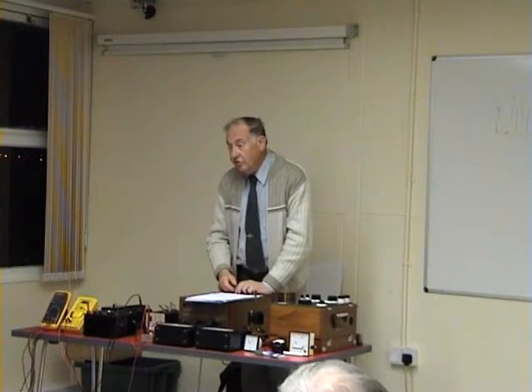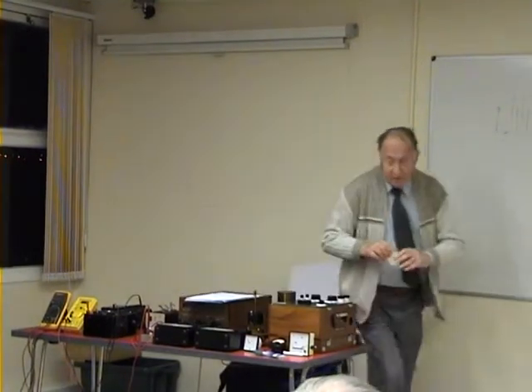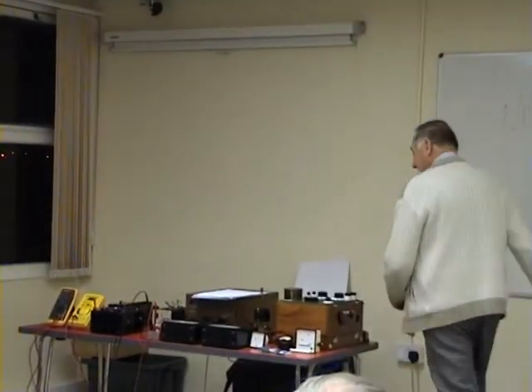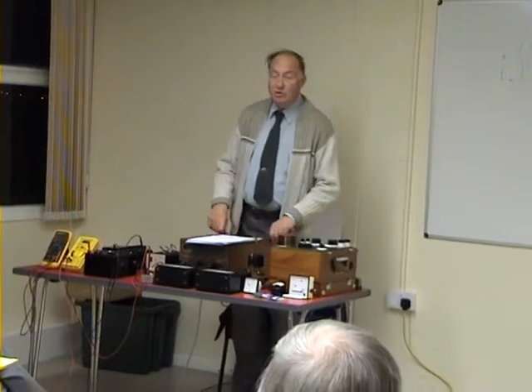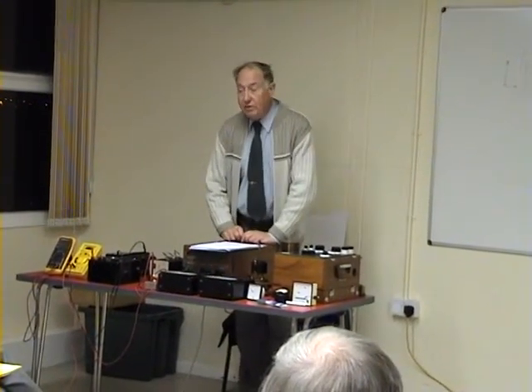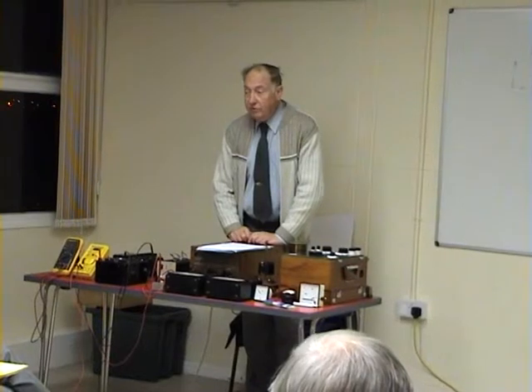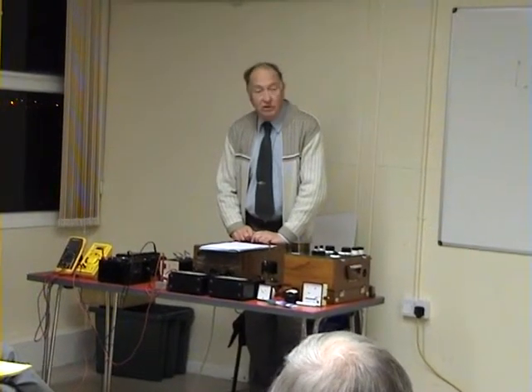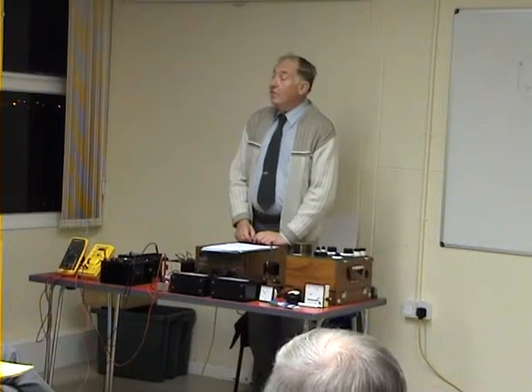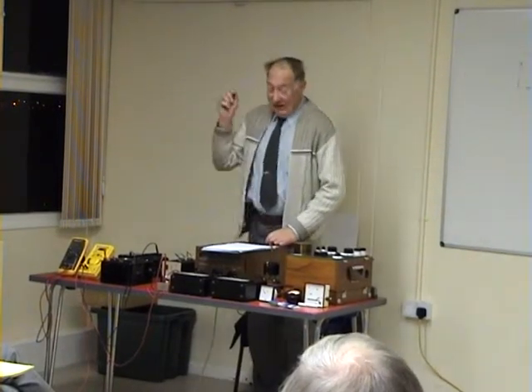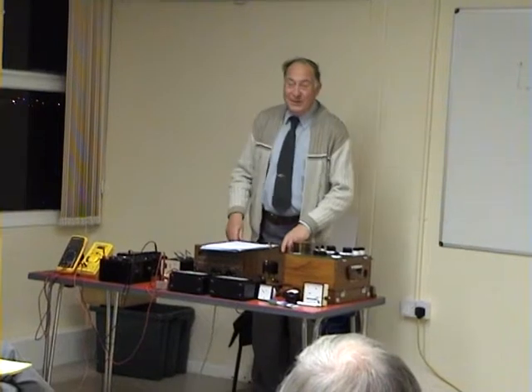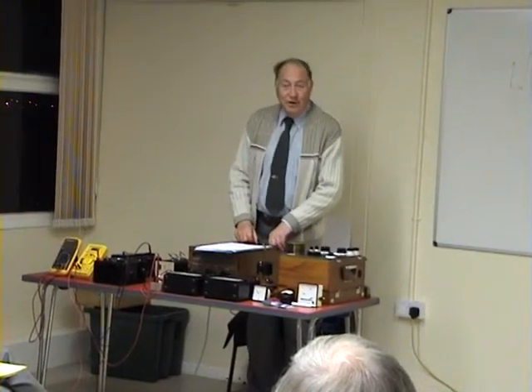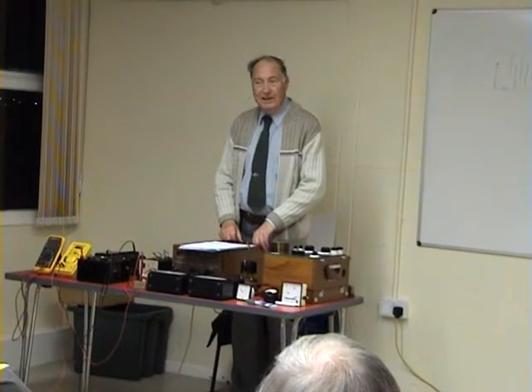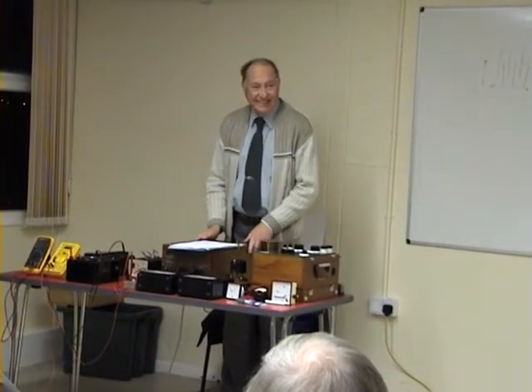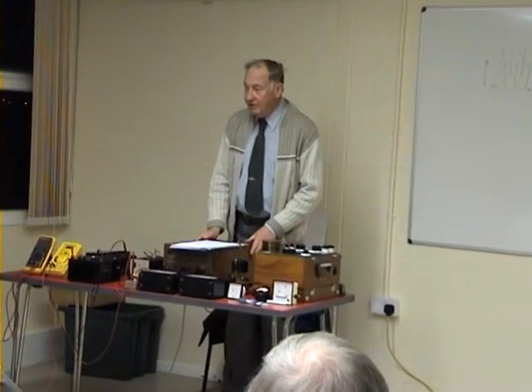On those you'll see the scale is very cramped at one end. Again it's a similar argument as to the moving iron, not for the same reason, but the device generates more current at the hotter end. The thing is with those, don't overload it. If you go over by about 5%, you're in the danger zone. If you're about 6% over, it's dead. They do not stand overload.